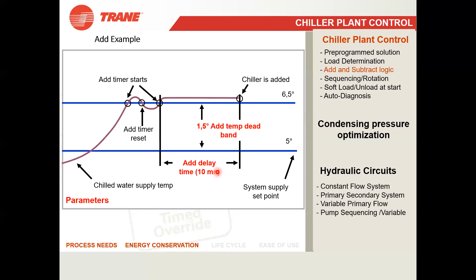So when will it start another chiller? If the chilled water supply temperature is at 6.5 degrees continuously for 10 minutes. There is a delay of 10 minutes. This delay I am giving as an example. The customer can customize this as per their choice. It can be 15 minutes or 5 minutes or 7 minutes. So if there is a delay of 10 minutes, the DTC controller reads that the chilled water supply temperature is at 6.5 degrees for 10 minutes. Then after 10 minutes, it will start another chiller. It will add another chiller. That's why it is called add logic.